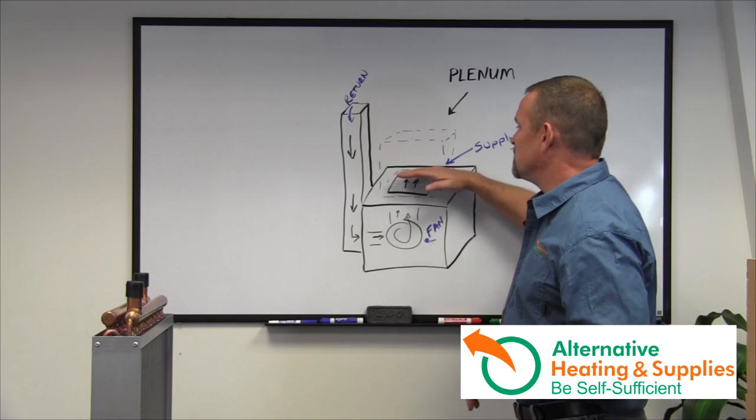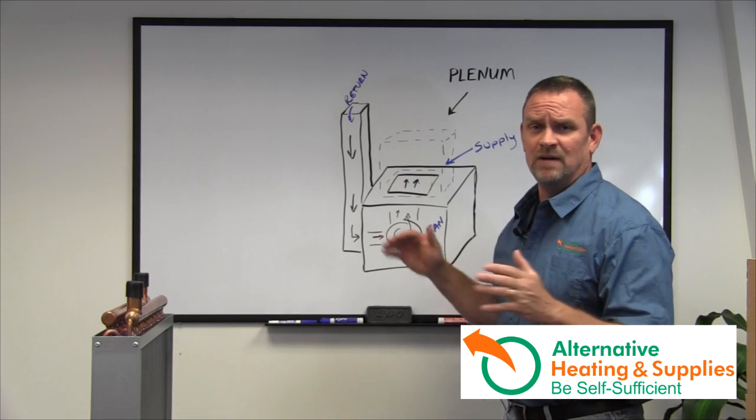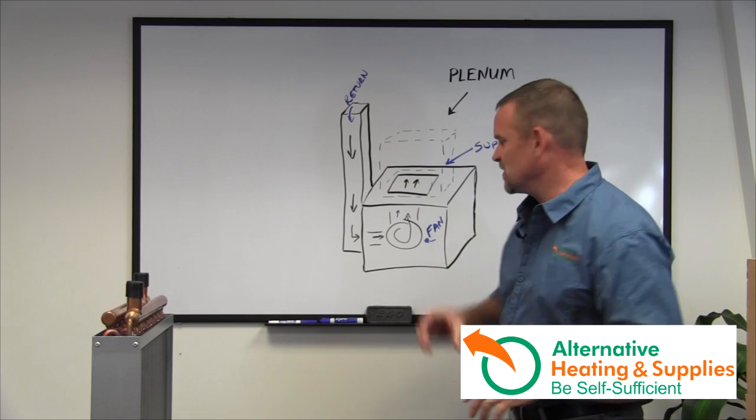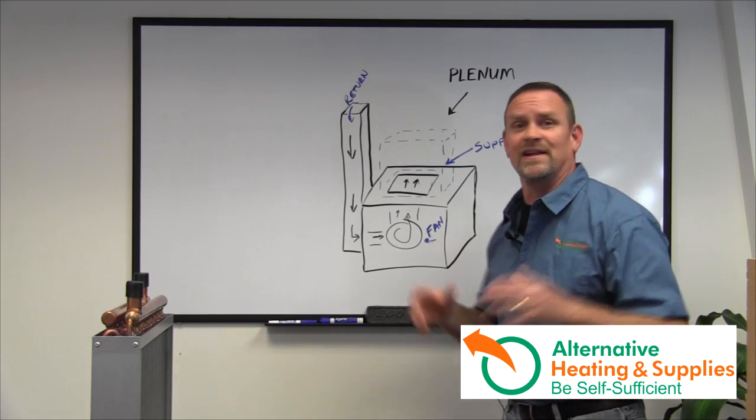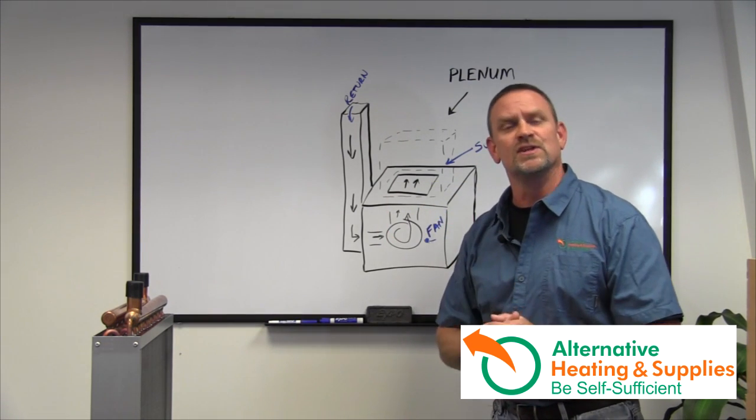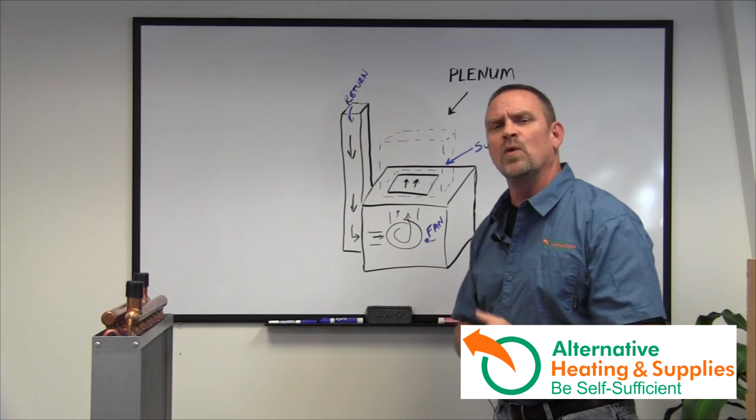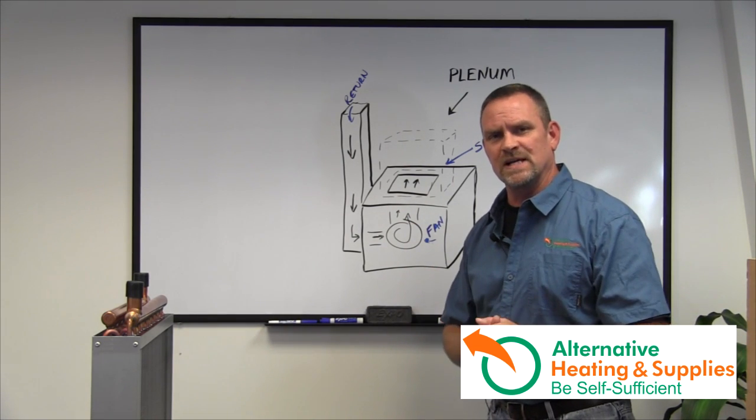So try to put your heat exchanger above any kind of sensors or anything else. They're usually mounted on the side and they're identified like a Honeywell or some kind of a silver box on the side. Try to get it away from that a little bit so it doesn't trip that sensor.